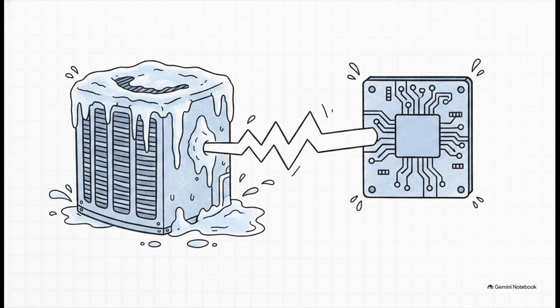Now, the second major feature that gets totally ignored by standard AC maintenance is the defrost cycle. On those cool San Diego mornings, the outdoor coil of your heat pump can actually ice over. So the system has a built-in defrost sensor and a board to trigger a cycle that melts that ice. If this isn't checked, and it happens to fail, your system will literally freeze up. And again, an AC-only tech? They're not even looking for this.